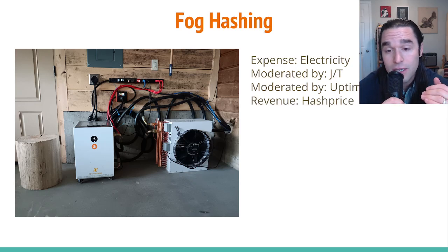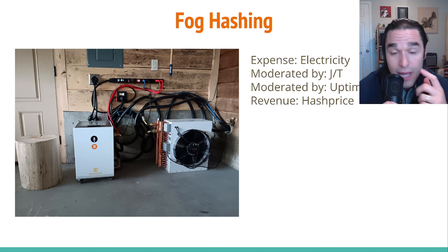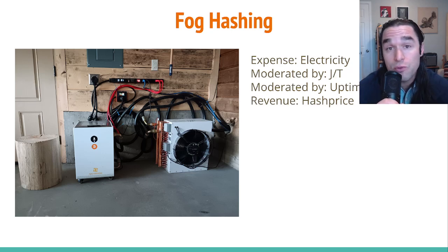And the beautiful thing is that I'm moderating it with this closed system, this immersion cooled system, which means that I'm not really subject to a lot of the issues of large environmental risks. I don't have to have a giant dry cooler sitting outside. This looks like a semi-indoor space, like a basement or a garage. It doesn't look like I have to really worry about this thing getting gunked up or getting a bunch of dust in it or freezing over at some random point in time.